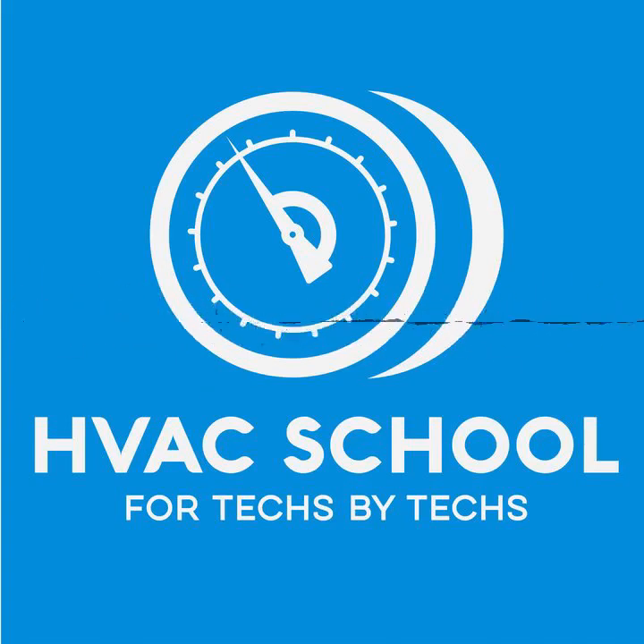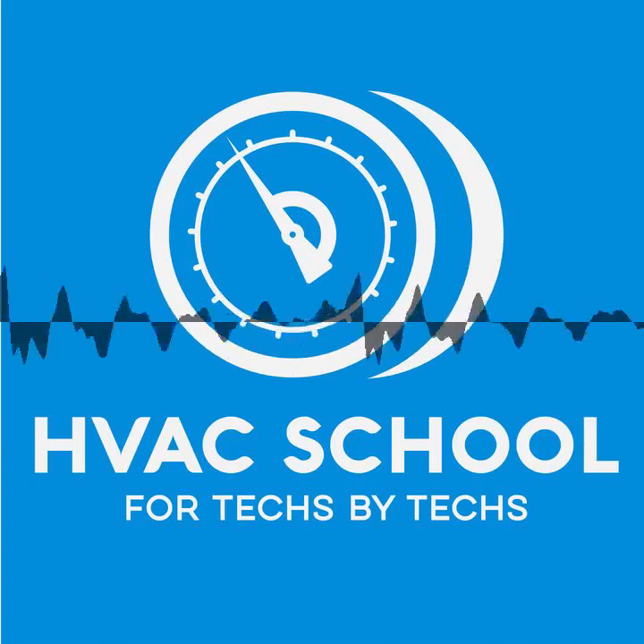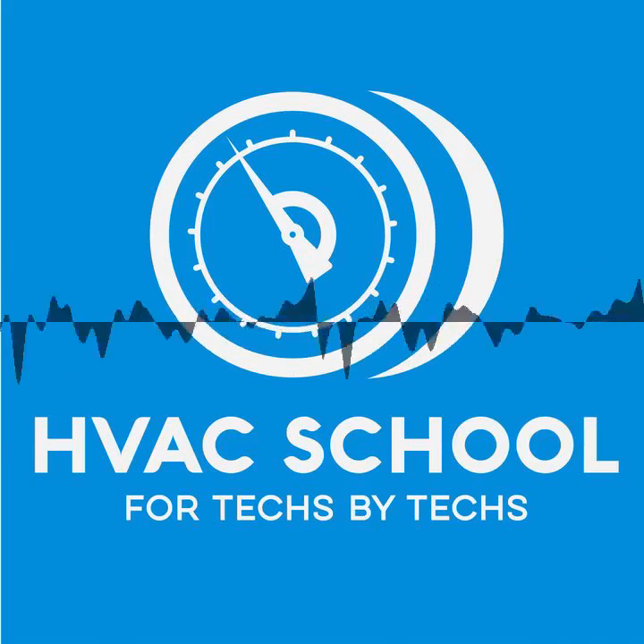Number one is some TXVs are hard shut off TXVs, meaning that without pressure in the system, there's no flow through the TXV, and you'll only be pulling from one side of the system. And guys will say, but I can tell that because I have my gauge connected to the liquid line. And if I don't pull all the way through, then I won't register vacuum. And hey, they are 100% correct.